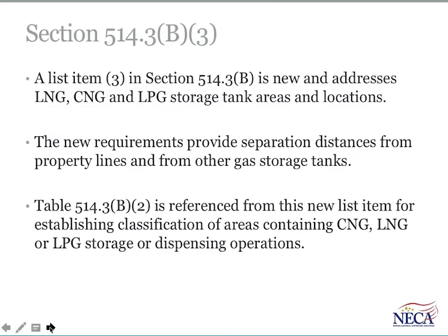Article 514 handles motor fuel dispensing facilities, and a new list item 3 in Section 514.3(B) addresses LNG, liquefied natural gas, compressed natural gas, and liquefied petroleum gas storage tank areas and locations. It's important to delineate the extent of the hazardous location for equipment selection purposes, wiring method selection purposes, and so forth. The new requirements also provide separation distances from property lines and from other gas storage tanks.